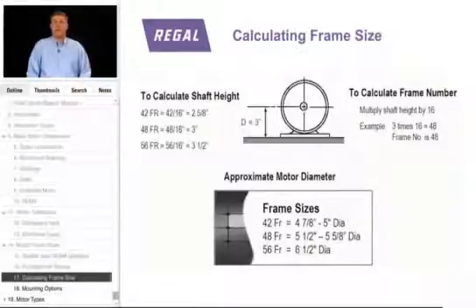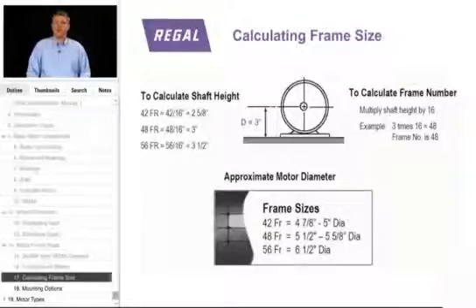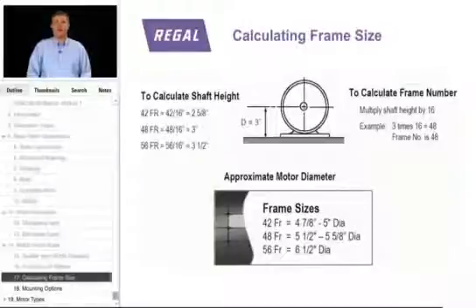Most contractors believe that is why we use the diameter of the motor — because the diameter helps us determine where the center of shaft is. On a 42 frame motor, the typical diameter is 5 inches. A 48 frame motor is about 5 and 5/8 inches. And a 56 frame is 6 and a half inches in diameter.